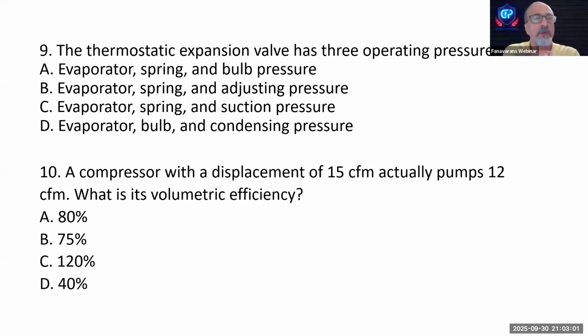We talk a lot about the thermostatic expansion valve, and lots of questions come from TXVs in the exam. We have 3 different operating pressures in the TXV. The TX valve has a body, an inlet and an outlet. We have the diaphragm, and we have a needle here. When this needle moves, it's because it's connected to the diaphragm, and the diaphragm is connected to where?